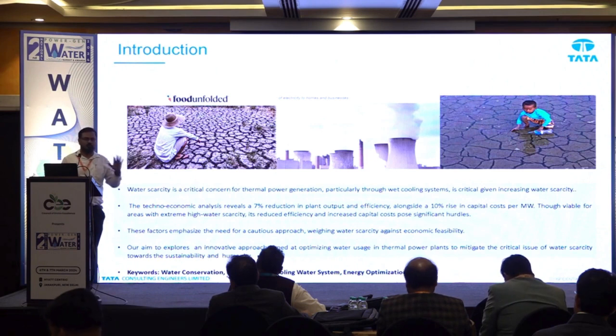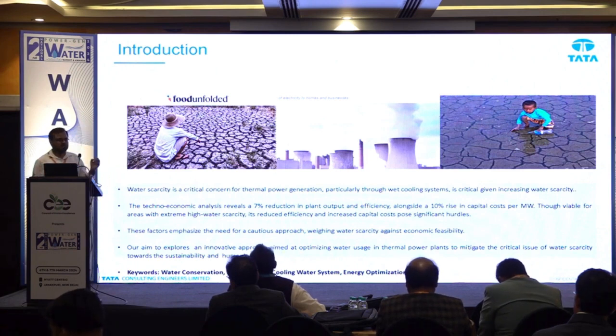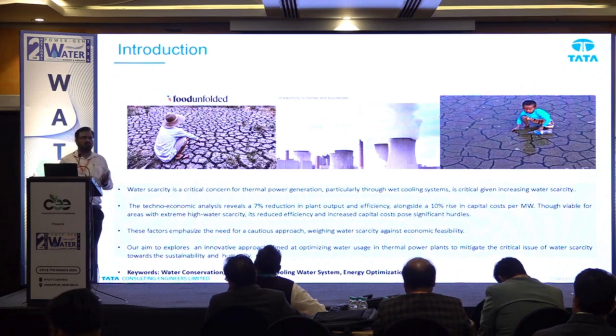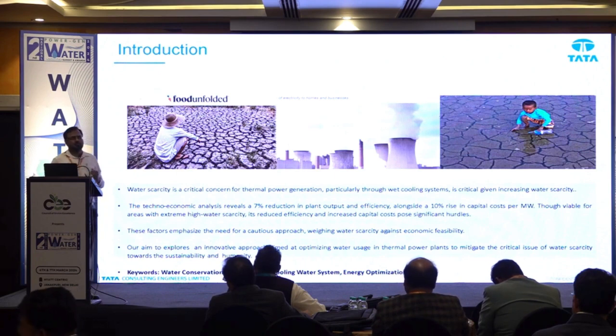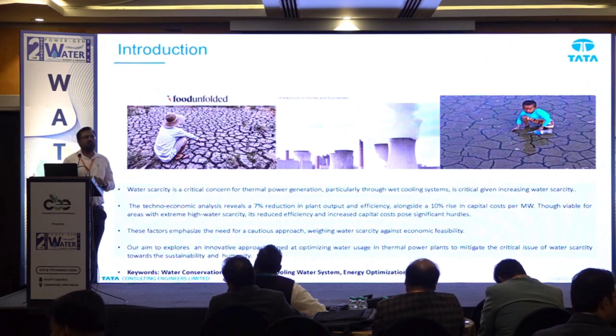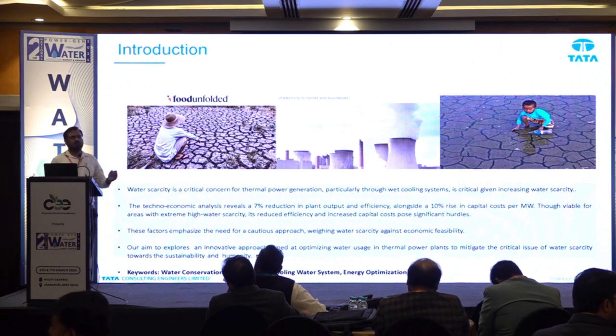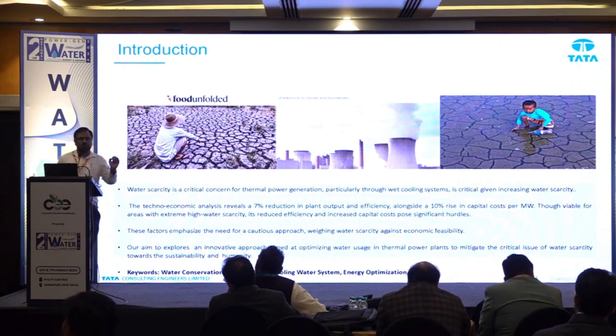So the main chunk of 70 to 80% is the evaporation loss and makeup, blow down and drift loss. Drift loss is 0.05, so that is less. But blow down is one factor, and another factor is the evaporation loss. If our aim is to reduce these losses, and we are able to succeed on this chunk of the cooling water, we will be able to reduce it.